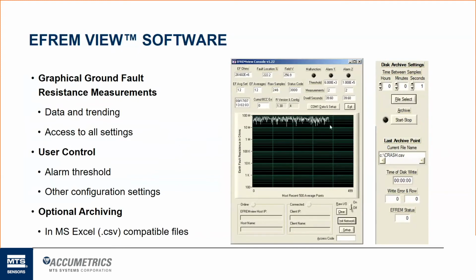When this resistance starts to drop and gets below that 500 k range, it becomes a much more linear plot, and the graphic interface really starts to show the resistance more accurately. So again, the customer should not have any concerns. This would be a healthy rotor. This is what we would normally expect to see, that scatter pattern up above at least 1 megohm. Usually, on a good rotor, it's in that 10 to 80 megohm range.